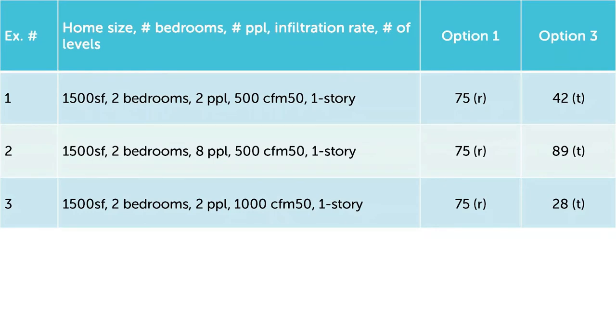Let's compare the two ventilation options using some example homes. The lowercase r stands for rated capacity, or not tested, and the lowercase t stands for the flow rate actually being tested. See how the only difference between example homes 1 and 2 is that 6 more people are living in the same house? We all know that house is going to need more ventilation, but ventilation option 1 doesn't account for that. Option 3 does. The difference between example homes 1 and 3 is that house 3 is twice as leaky. Ventilation option 3 accommodates for this by requiring a bit less ventilation.